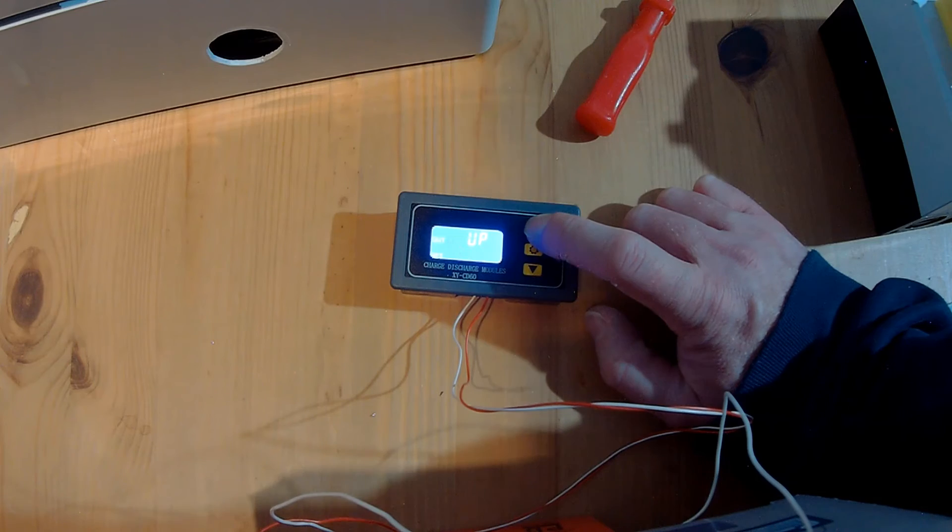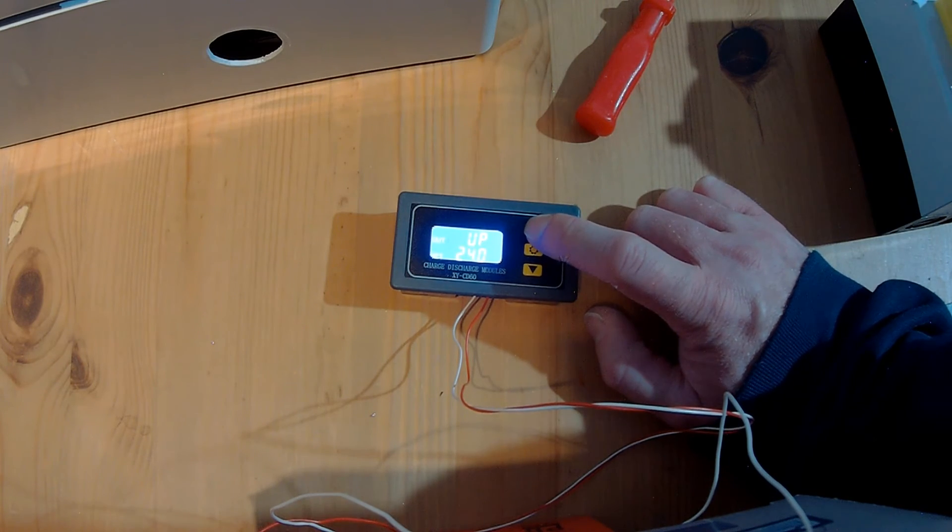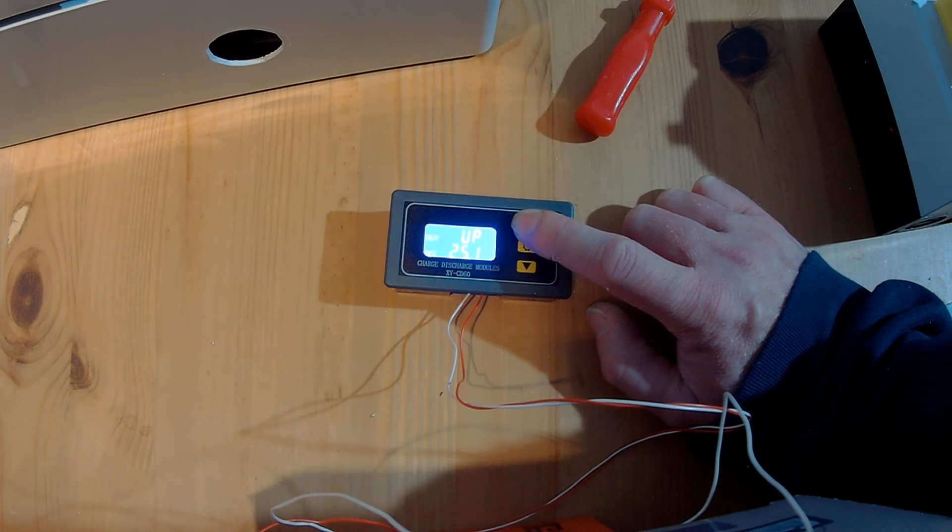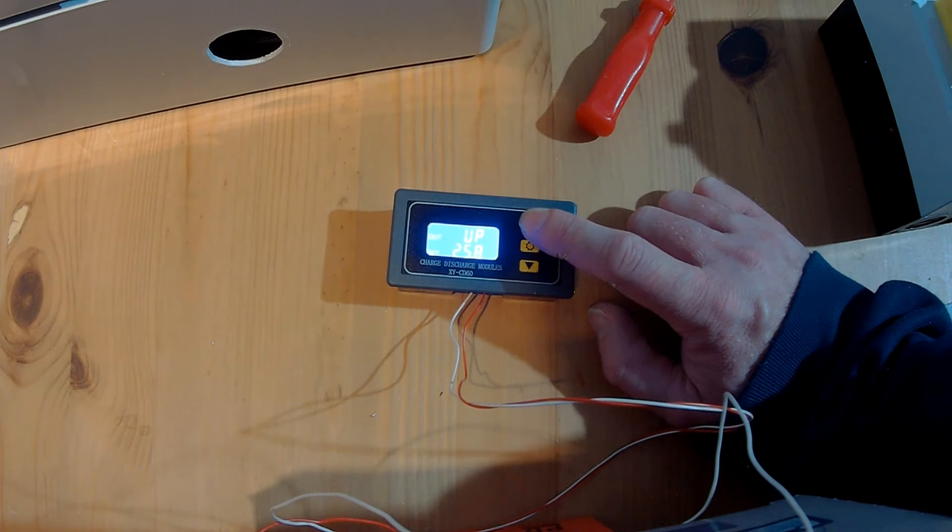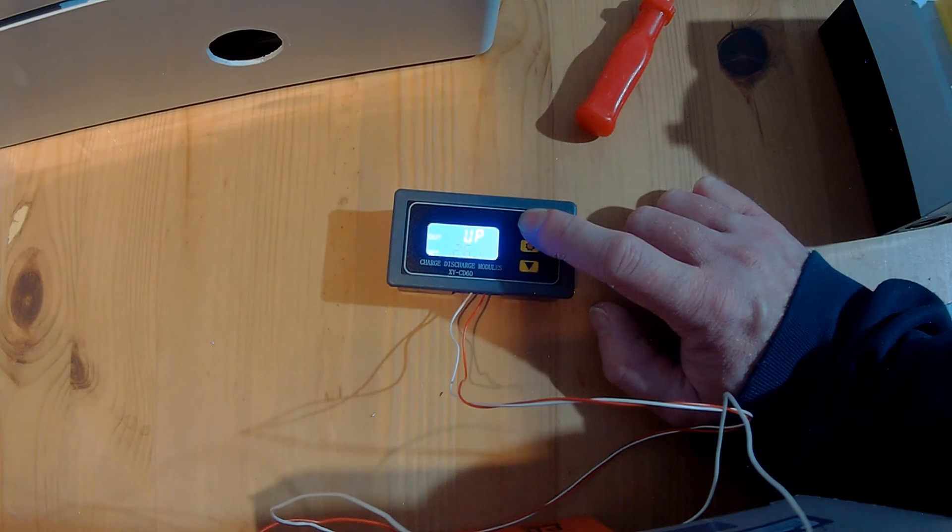So for a 24-volt system, for example, I would set the up probably at 28.9, 29 volts for lithium iron phosphate batteries. And the down at 28.5 for example.